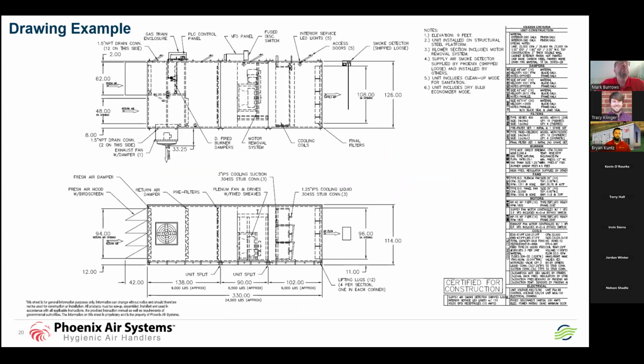So plan view, of course, whether it's, again, 3,000 CFM or 100,000 CFM, it doesn't matter. Fresh air intake, mixing then with the return air going through a pre-filter bank. Typically, this has the blow-through configuration, so we're going to heat the air up. Then the air off of that goes into the cooling coil. The air off the cooling coil would then either hit a reheat coil or go directly into the final filter.